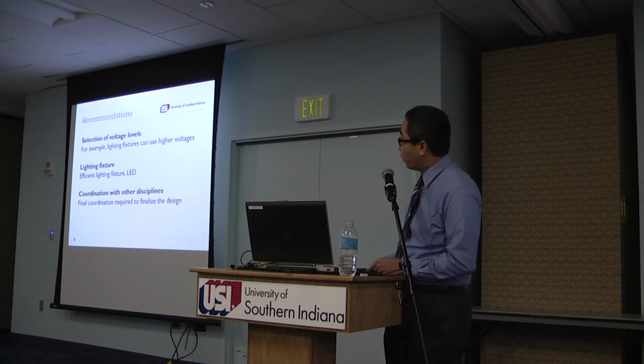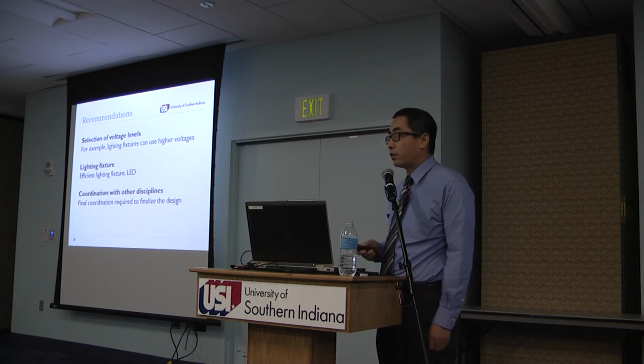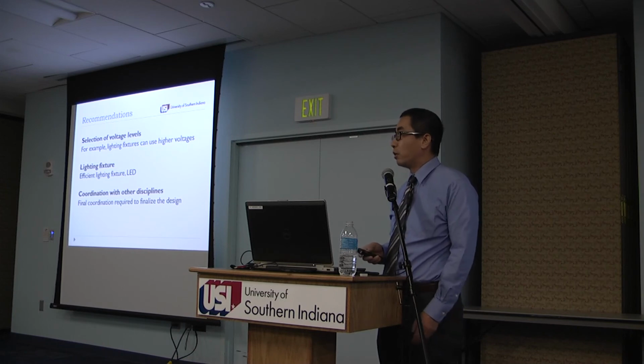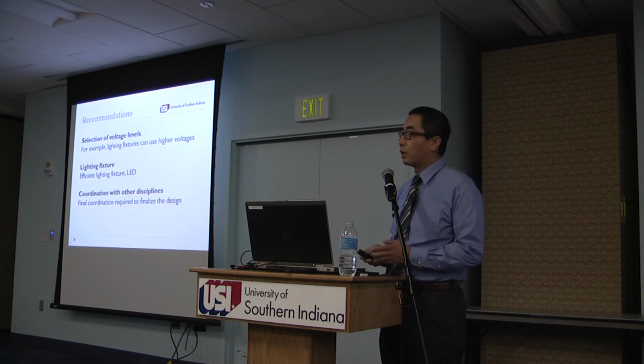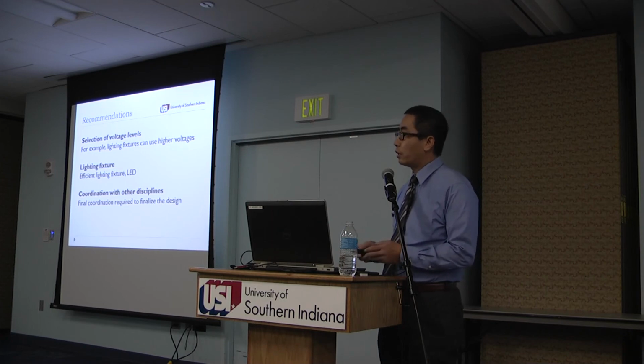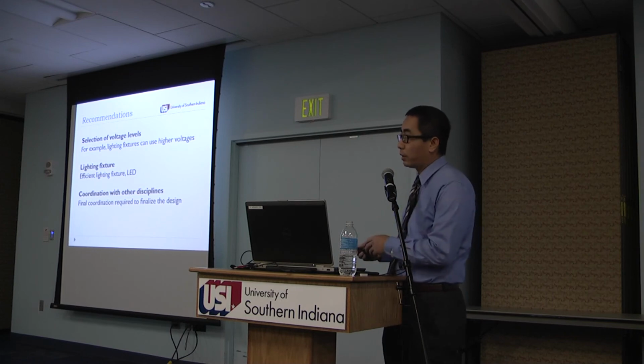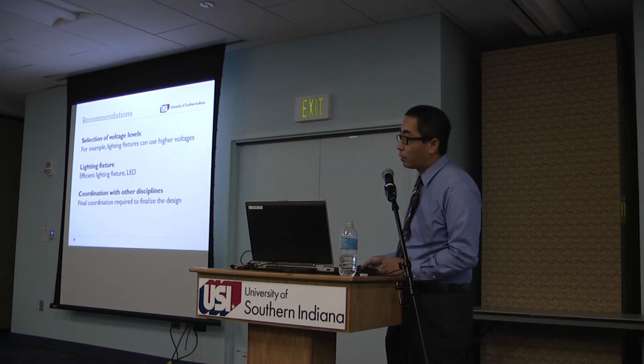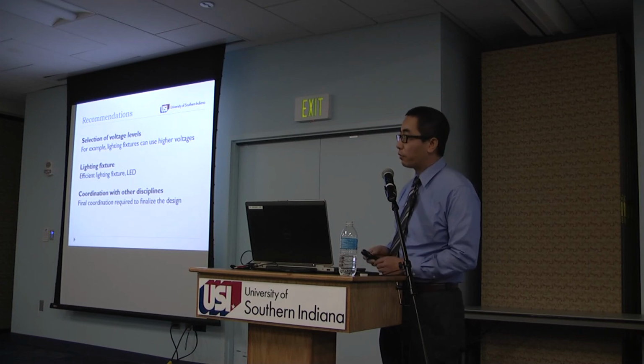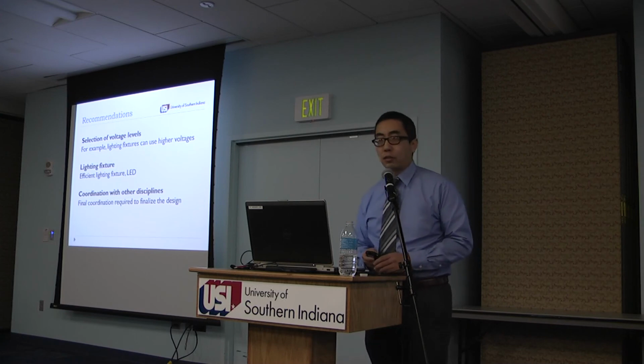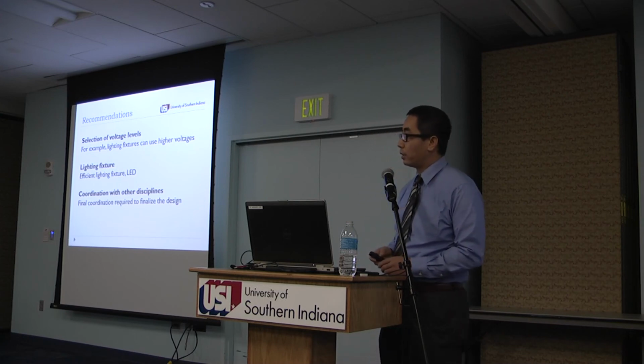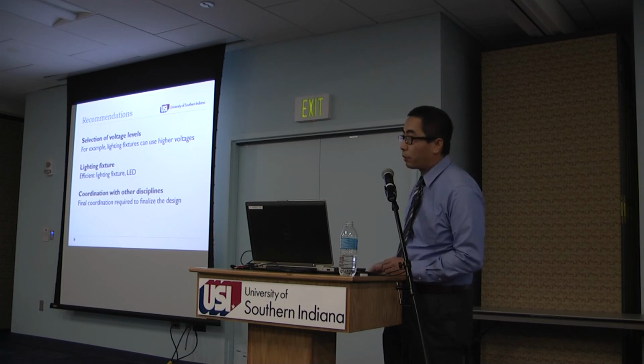And for the lighting fixture, we use the fluorescent lighting fixture for the whole facility, not just this building. So we think that if one of them burns out, once a year we'll go there and replace all of them. If they're not burned out, we use them on other buildings. But now LED lighting is more and more cost effective. It's still more expensive up front, but it can save you some energy and cost in the long term. So that's something we need to do some study on. Basically, just initial investment versus long-term cost saving.